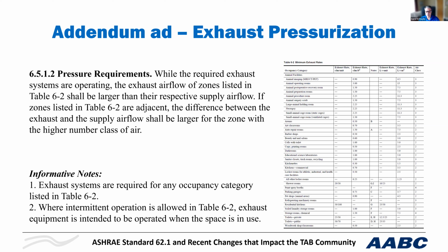And then you have supply fans that are variable. They may be one speed or another speed. So you have a really dynamic system. You have exhaust turning on and off, you have supply turning on and off. So it's a lot more complex than you think to maintain that negative pressure. And you have spillage of air and you don't have the right amount of exhaust, and you have air that's not so good. So this requirement is to ensure that you're going to have a negative exhaust pressurization, and then you have the controls to do that.